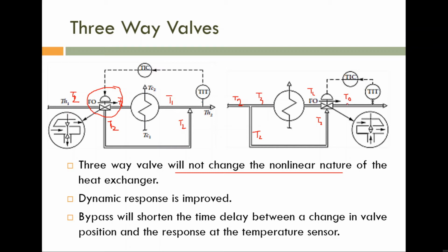We all know that due to temperature, a thermal expansion will be there. But due to different temperatures at different points of this control valve, the thermal expansion will be different because we have a temperature gradient problem. So the thermal expansion is not unique. So it will result in a maintenance problem, failure. So the life of that control valve will decrease here compared to this control valve. So this instrumentation is favorable. Please note that. For the remaining explanation, I am using this instrumentation.